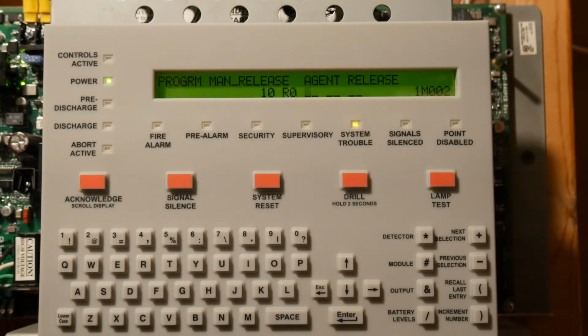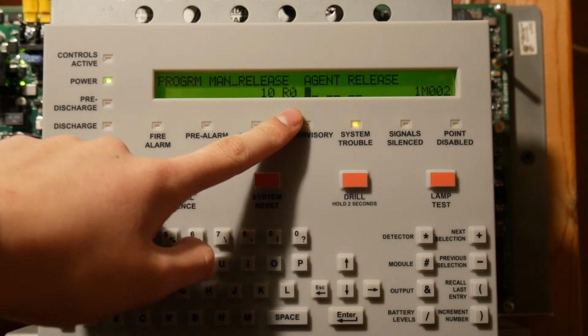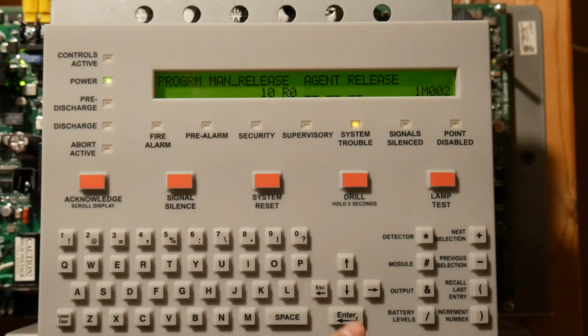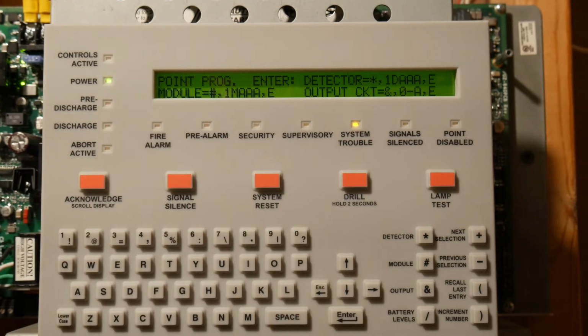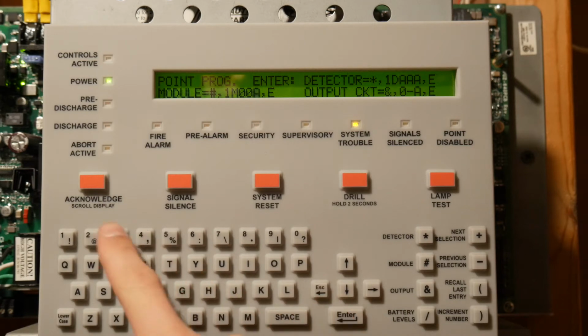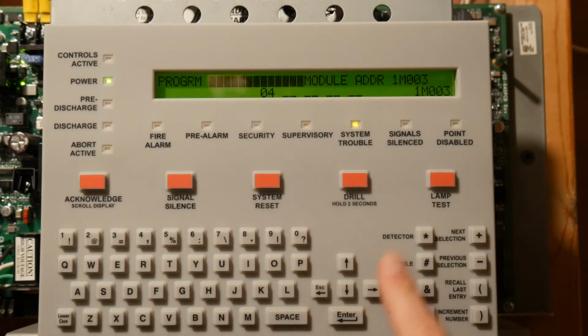Releasing zone 0 is where you can map a NAC. I'll show you what special functions are in a second, after I'm done programming the points. So we're going to module 003. Module 003 I have set as a pull station, so we're going to set that as a pull station, and this is basement pull.